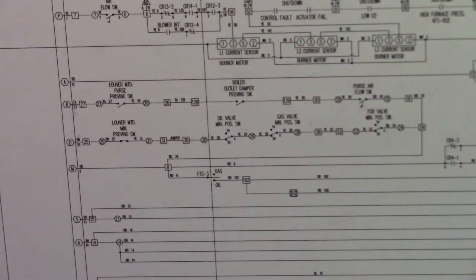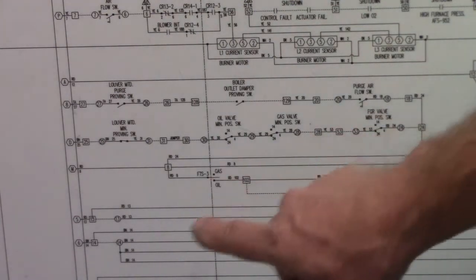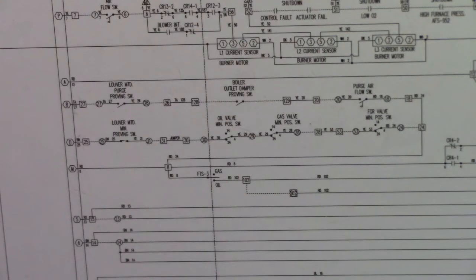This switch is the inlet damper for the fan, sometimes called a high fire switch. So in the M8 loop, there are only three components. The FireEye is telling us that one of those, or more than one, but at least one of those components is preventing the boiler from going into purge.